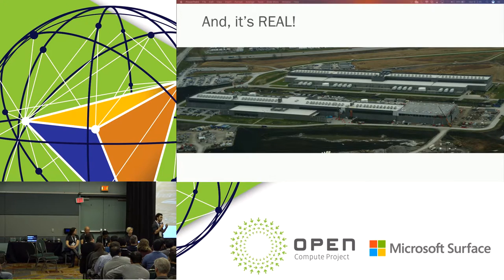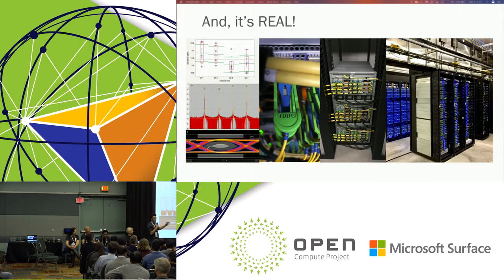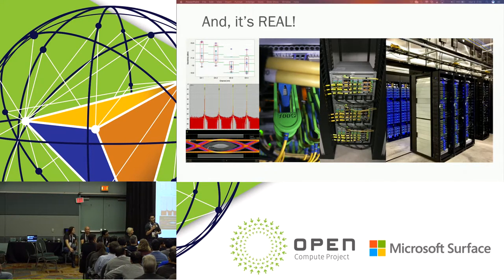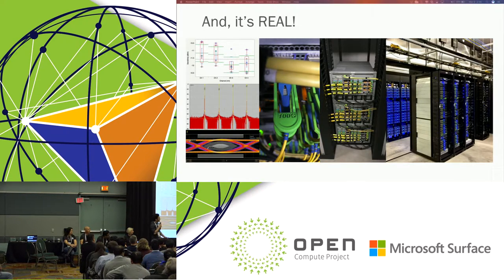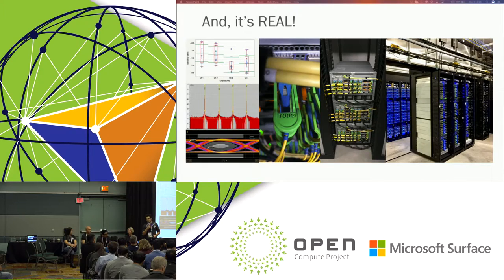In order to do that, we need to do a very good job in terms of our qualification. We go through a lot of various stages, starting from a component and module level, progressing to system level tests, and then data center level tests. As we go from stage to stage, the blast radius of failure at each stage grows. If we're doing data center testing and we have failures at that point, it can have significant impact. Whereas if we catch everything in component and module level testing, we become much safer in terms of potential damage. So it's very important to have data-driven progressions through each stage.